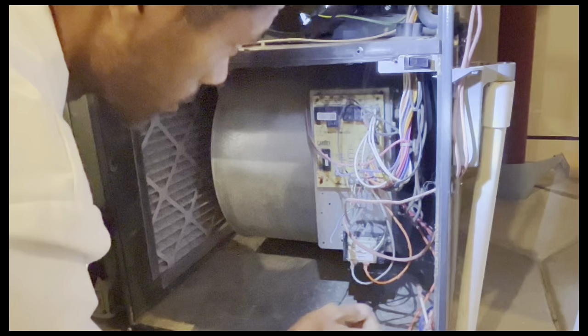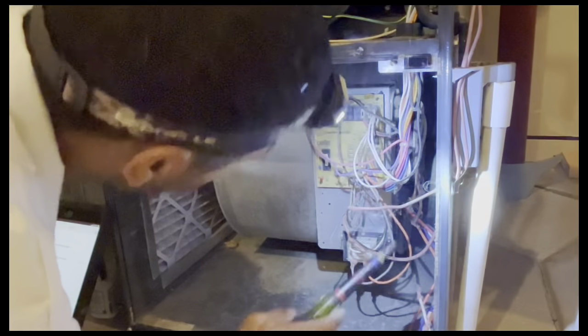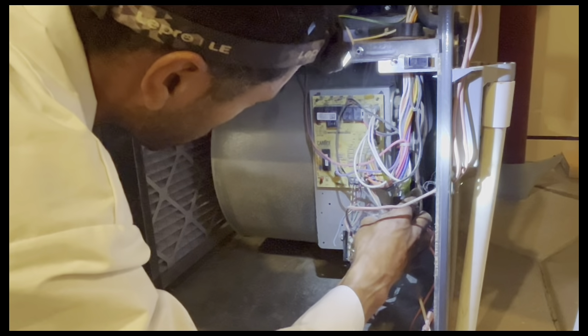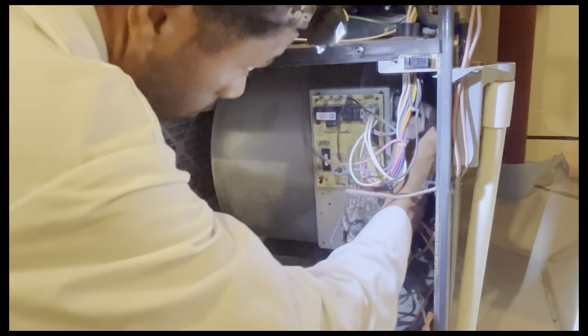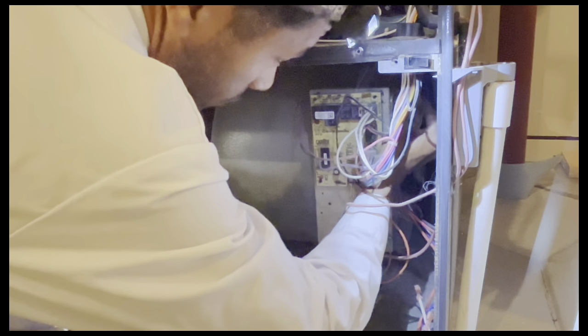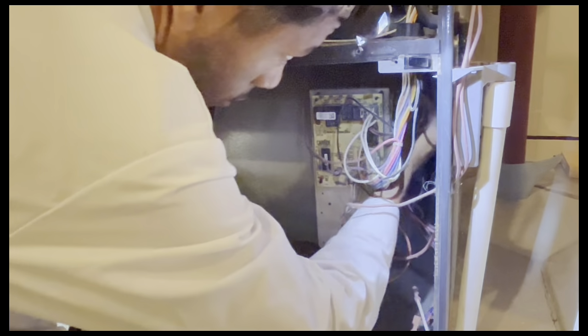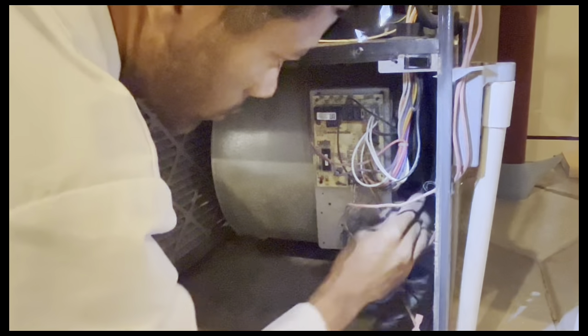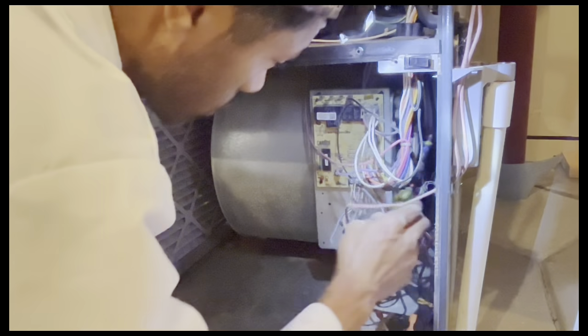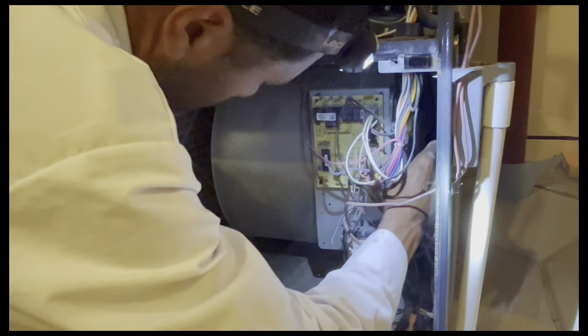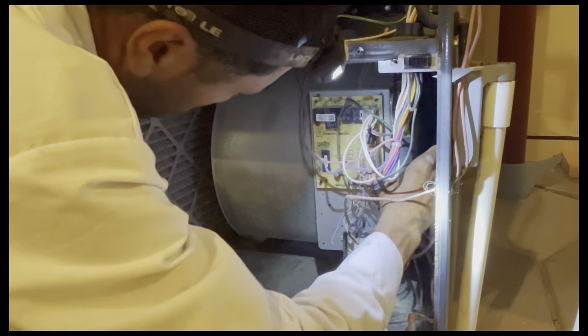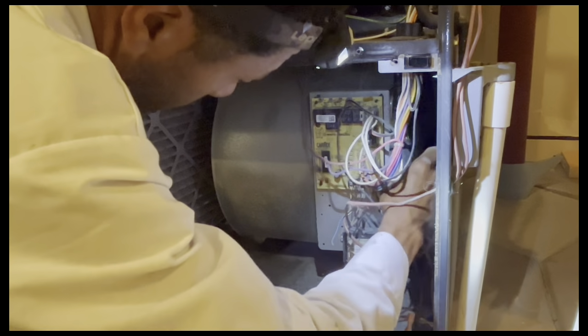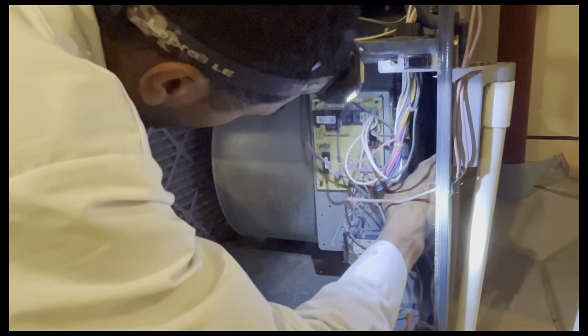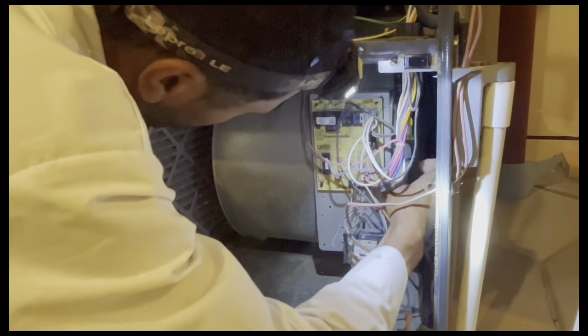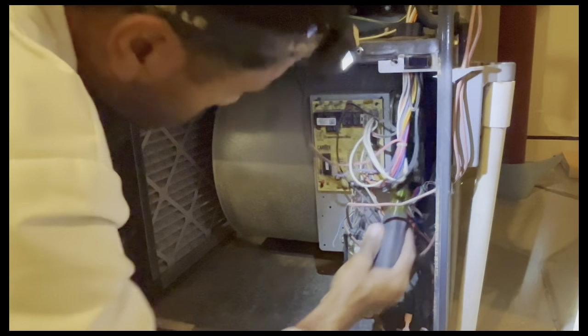So I'm taking these wires off for the blower motor. Those are the different speed taps. Looks like that one may be a 4-speed blower motor. And then if I remember correctly, that's probably the capacitor wiring there. So that's a PSC blower motor. That's a permanent split capacitor motor. It's an older style. It needs a start run capacitor to operate.